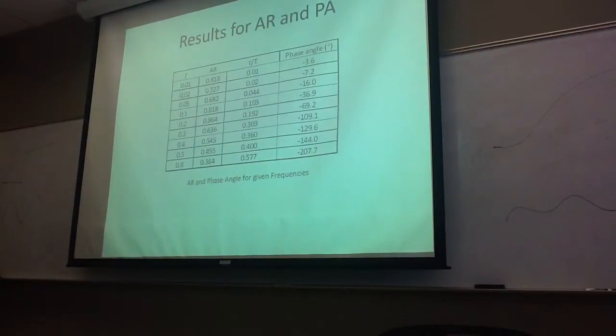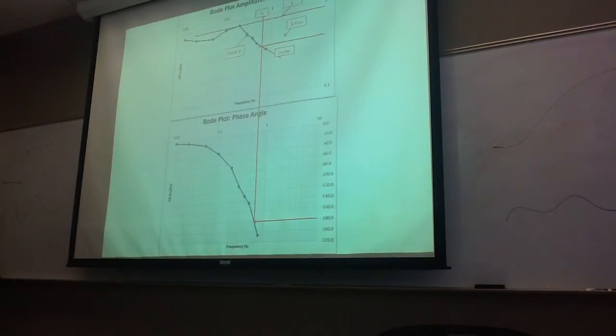Now the important part is we're going to plot both the phase angle and the amplitude ratio against the frequency, and that will allow us to read a few important values from the Bode plots. And this is how that's done. If you look up here, you can see the ultimate frequency, the K, the KCU, and the order can be determined by reading these plots as indicated by the red arrows.